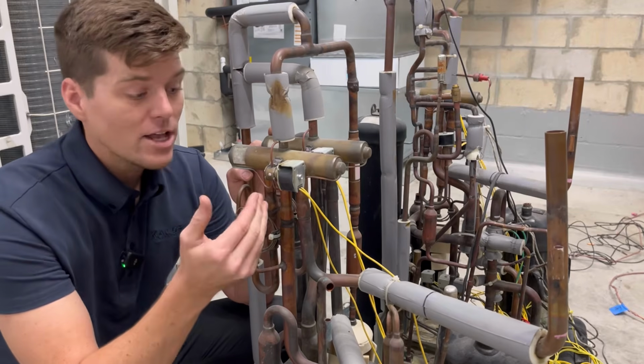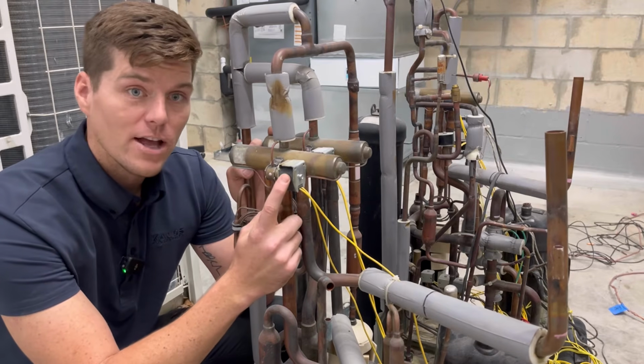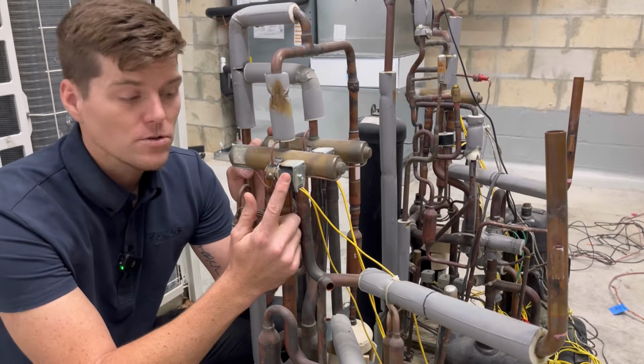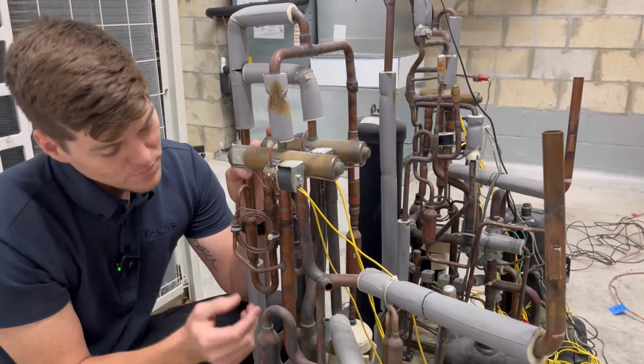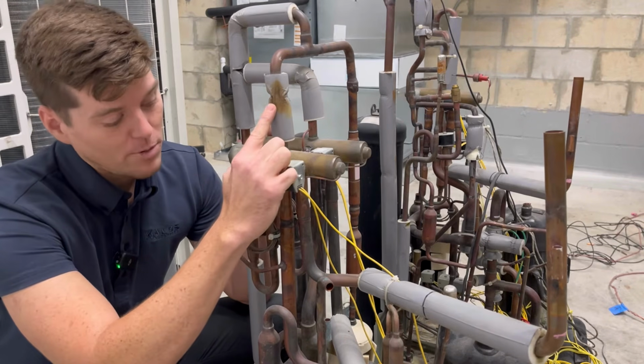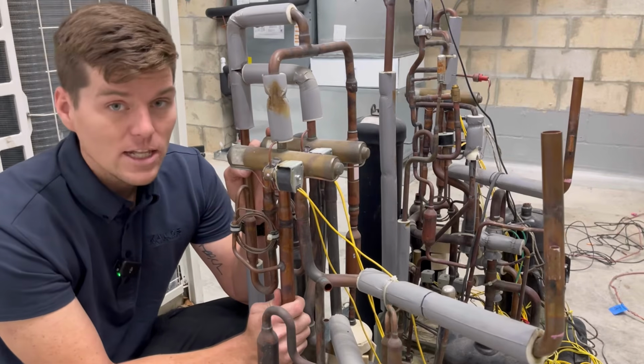A four-way valve that will not shift when energized, right, with a solenoid on the outside here, whether it's 120 or 240 volts, not allowing it to go from left to right. Notice here that because this is always high pressure state, the suction line is always in a low pressure state, right?